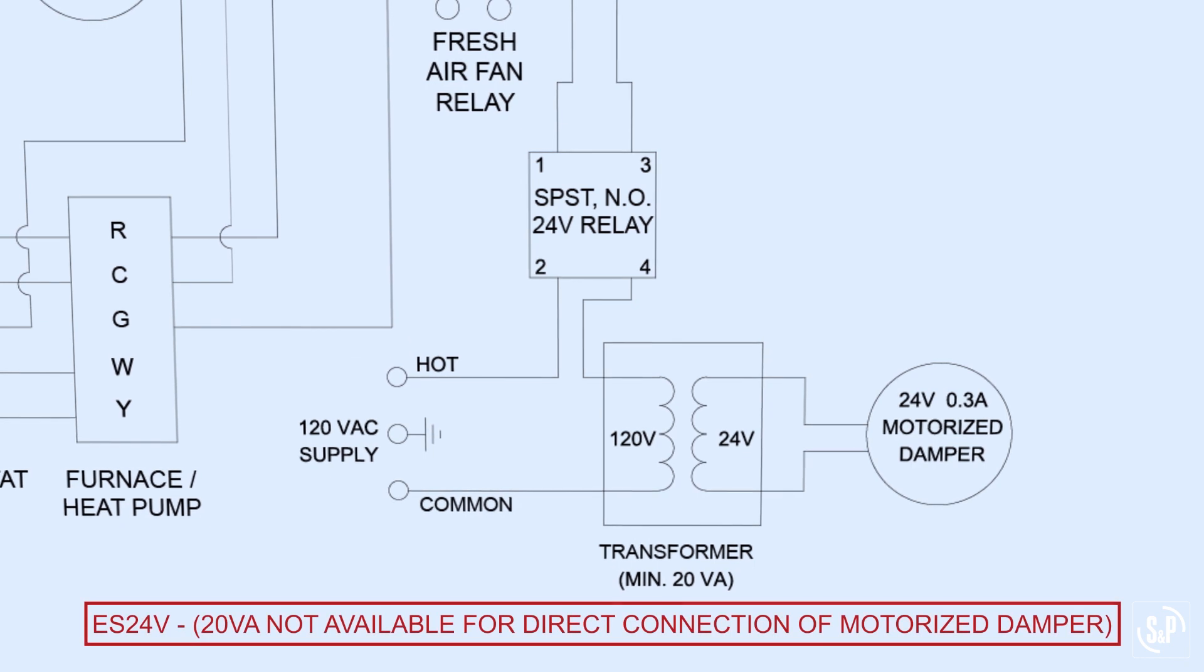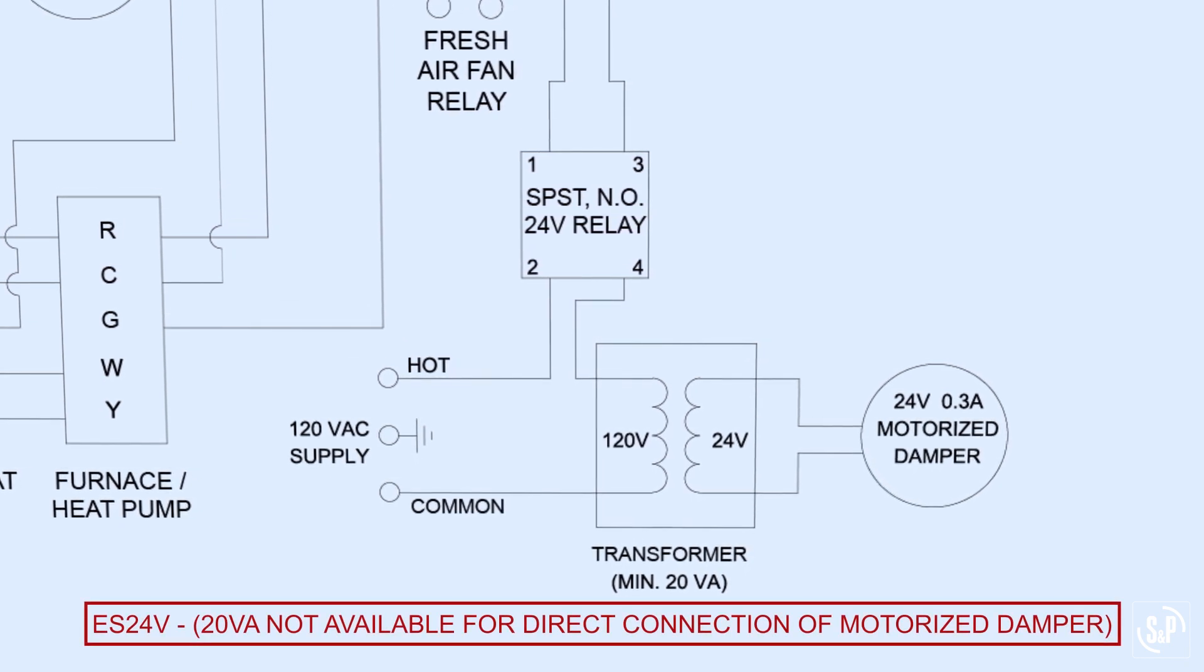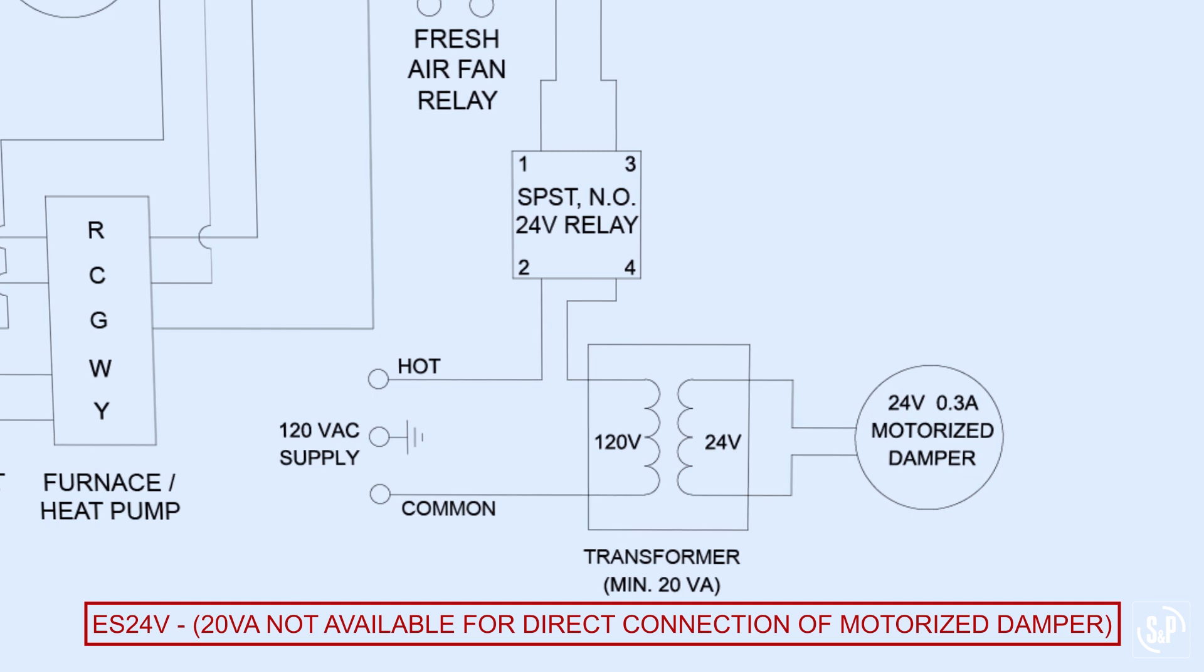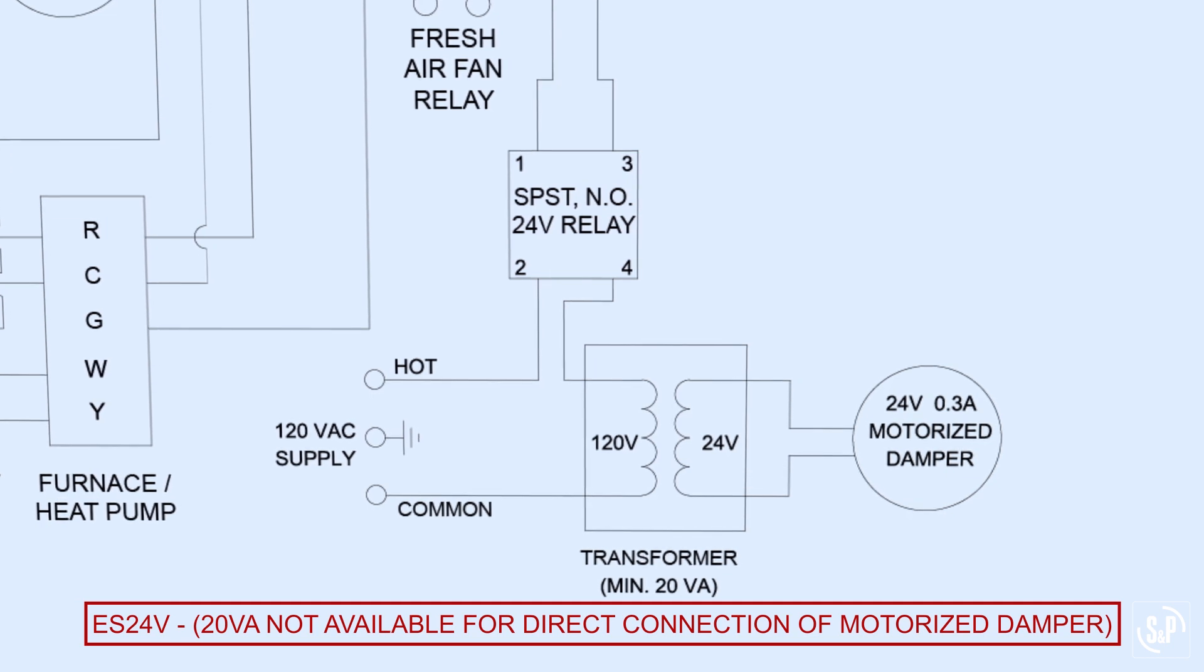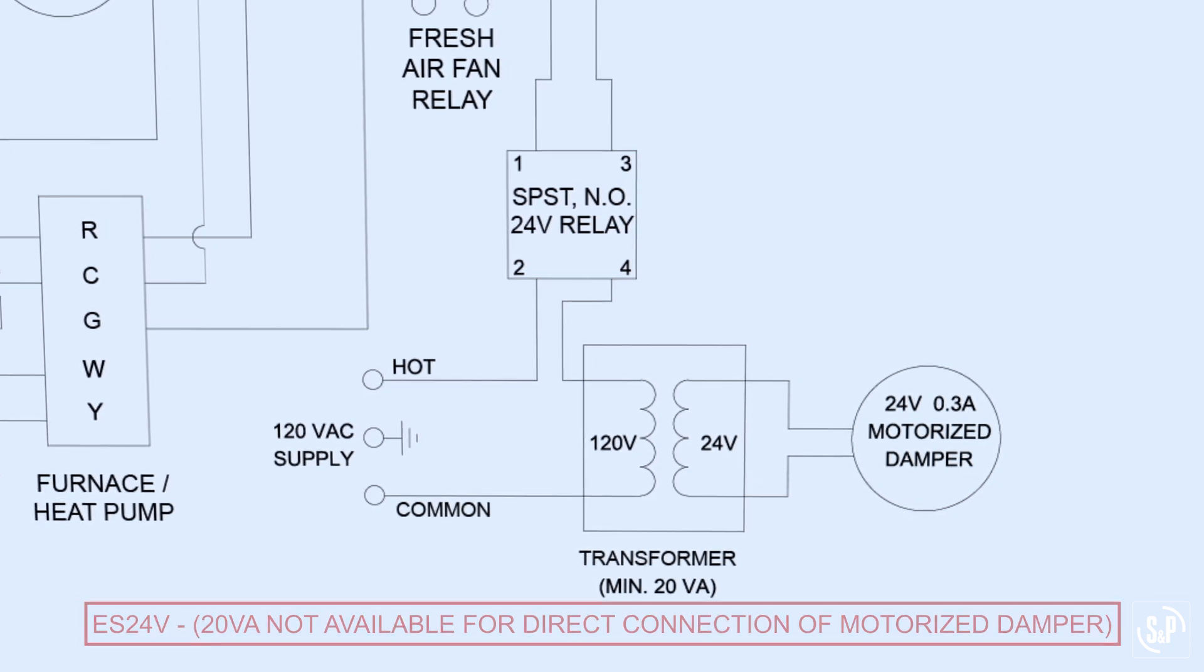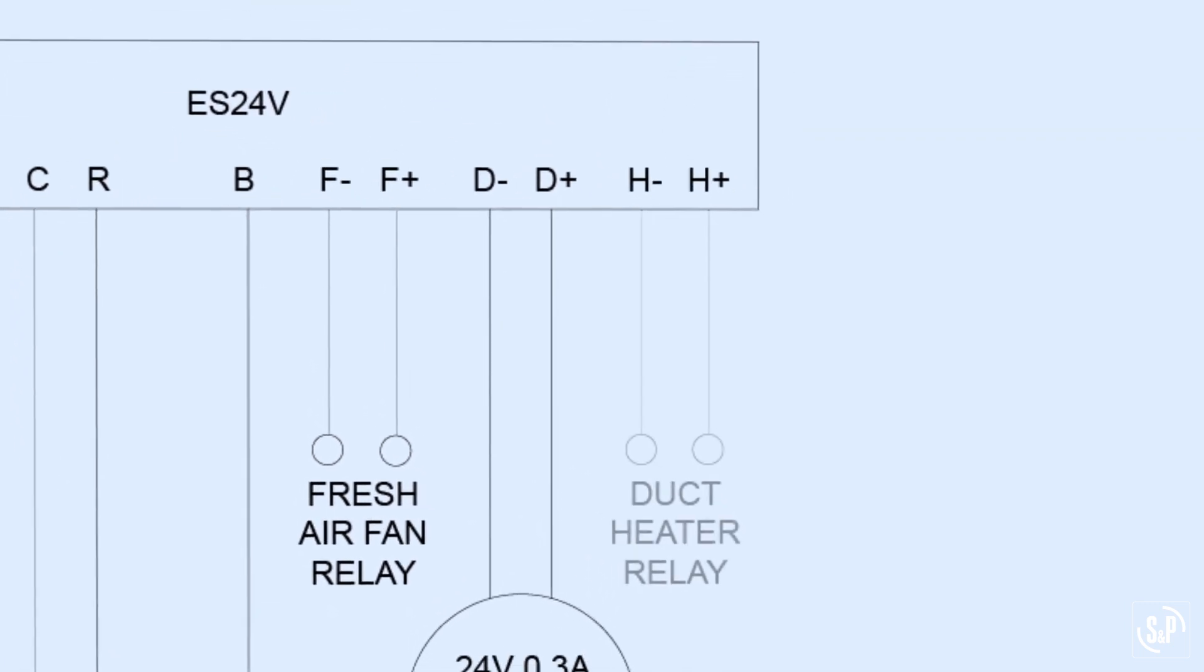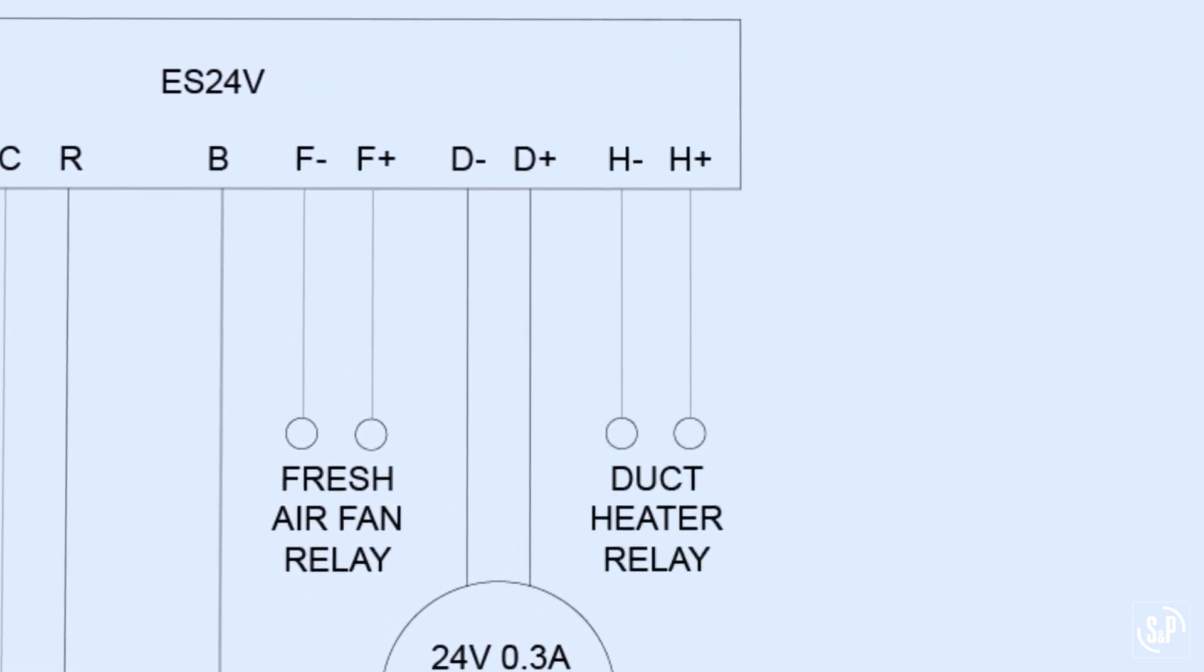We recommend at least 20 volt amperes of apparent power be available from the HVAC unit or auxiliary transformer if powering the motorized damper directly instead of through a relay powered separately. The H negative and H positive terminals connect the ES24V to the duct heater relay.